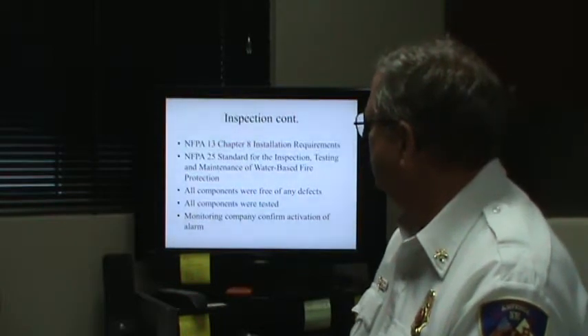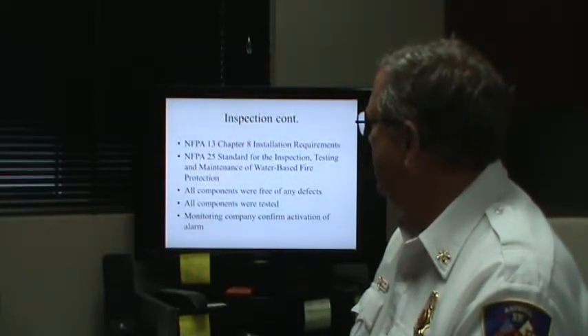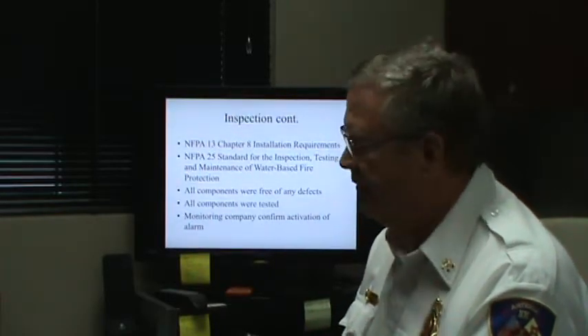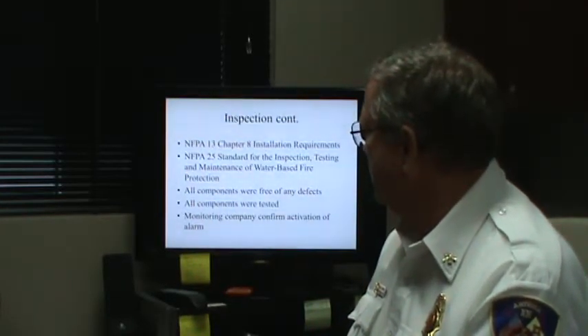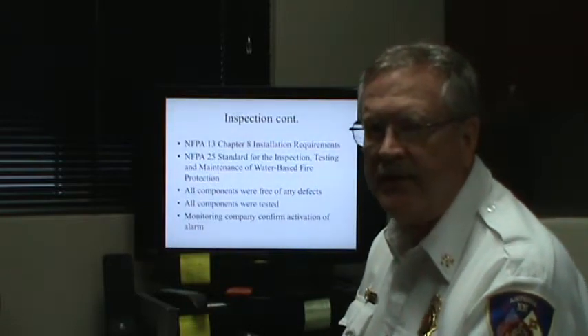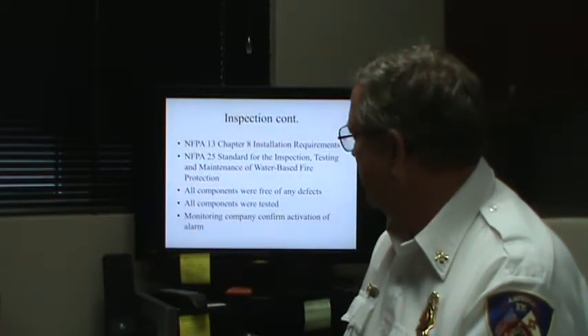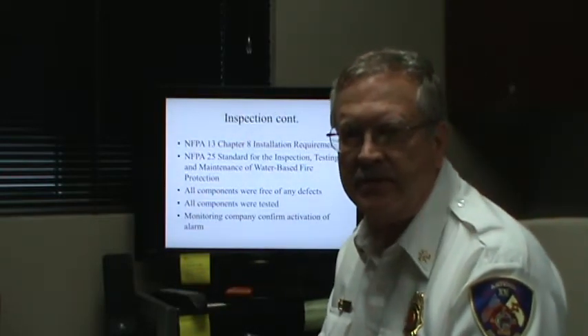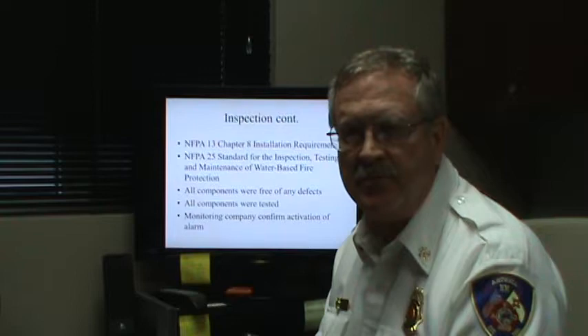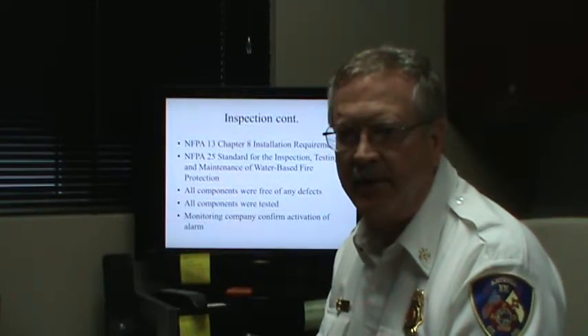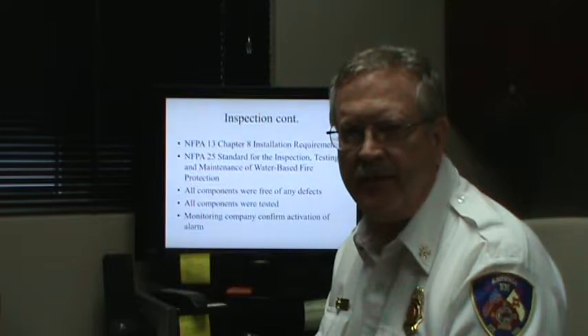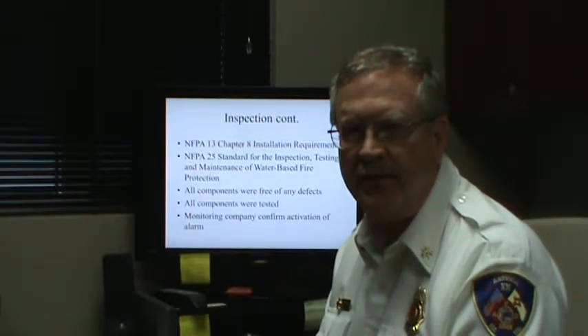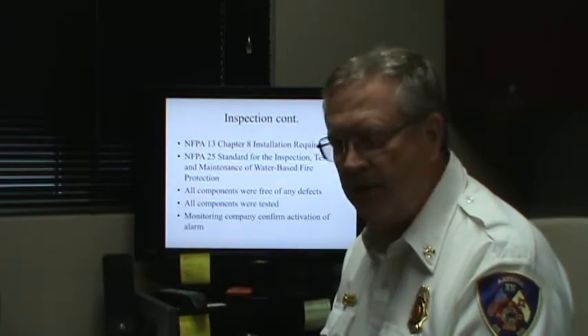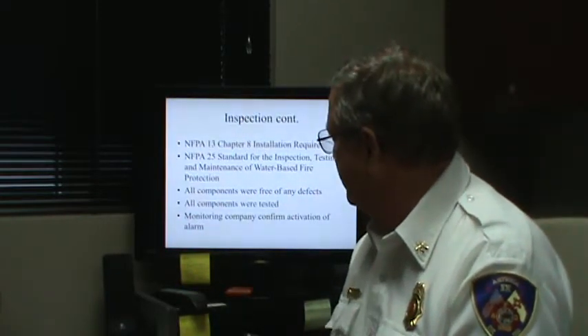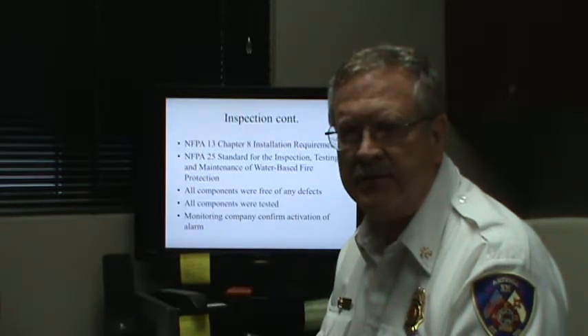Okay, that NFPA 13.8 installation requirement was for the elevator part, and NFPA 25 is for the water-based systems. This was a visual inspection of the components: the sprinkler heads, the alarms themselves, the detectors themselves. I couldn't get up into the ceiling to check the dampers to the air conditioners, but that would have been part of the inspection. Sprinkler heads were good. I didn't notice any leaks. There was no damage to them.